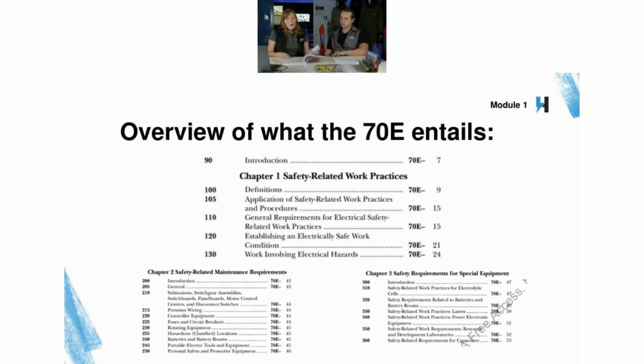And then it continues on and talks about permitting and safety programs and making sure that training is taken care of and that you've got a good lockout tagout program, and the qualified people are the ones doing the work essentially and overseeing the work. It talks about the different emergency response training you might need, host employer versus contract employer responsibilities. Essentially, just because you subcontract out some work doesn't mean that you pass the buck of liability, right? You still have to make sure that if they're coming to your job site or your workplace, that they also are following safe work practices. Test instrument requirements, just all sorts of things, good information. Article 110 is your starting place if you've not had a safety program or a lockout tagout program before.